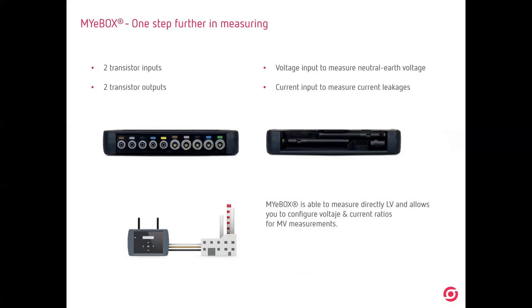For measuring the leakage, we have Wi-Fi and 3G antennas, and 2 transistor outputs and 2 transistor inputs. The inputs are used for reading pulses coming from water, gas, heat, or mechanical meters. So we are not just taking care of electricity, but of different sources and different consumptions. The input can also be used for checking the status of something, for example a protection on or off, or a detector. If the protection trips, the input will change status and we will be able to send an email. If anyone opens a switchboard, for example, the input status will change and send us an email telling us something is happening inside the switchboard. Or it can change the tariff.